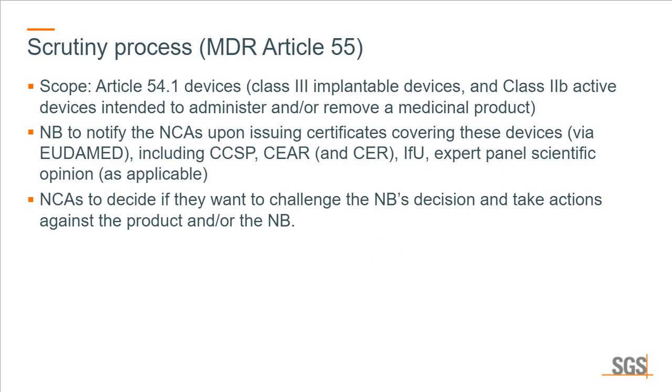The last thing that I want to talk about is the scrutiny process. So for certain devices, class 3 implantable devices, class 2B active devices intended to administer and or remove medicinal products, there is a scrutiny process. So the notified body shall notify the competent authorities upon issuing the certificates covering these devices via EUDAMED.